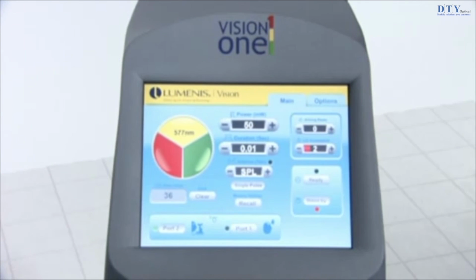The Vision One system has 2 different tones or beeps to signal system functions. The system emits a higher toned beep when it is able to perform the requested selection, and emits a lower toned beep when the laser is not ready, when the maximum or minimum treatment setting is reached, or when an error has occurred.